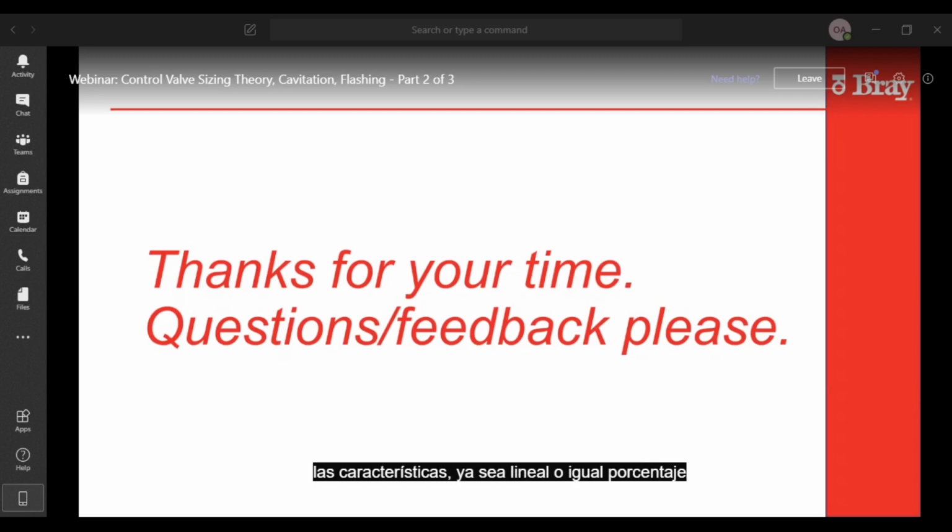We discussed that in part 1 of this series. And on a ball or butterfly, ball, you have kind of an equal percentage curve as well. So you can go further down and up on a ball. So let's say on the globe, you would be, let's say, 20/80. On a ball, you may be able to do about the same, 20-80% of the range. And on a butterfly valve, we're probably going more towards the 30-70. And why is that?